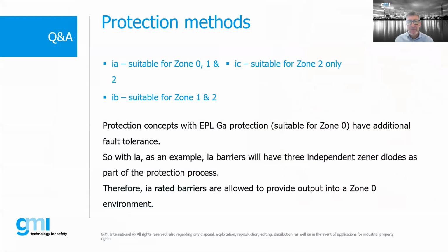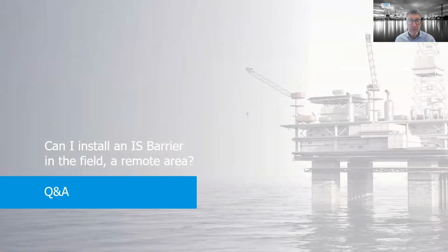There was a question about IA, IB, IC. What are these different protection concepts, advantages, how they can be used? IA is suitable for zones 0, 1, and 2. IB is suitable for 1 and 2. IC is suitable for zone 2 only. IA, as an example, barriers will have 3 independent Zener diodes as part of the protection process. It's a fault tolerance that allows these products to be used in a more onerous application. That's why we have 3 levels of intrinsic safety. It is a little more than just diodes, but yes, they are more fault tolerant, more safe, if you wish.